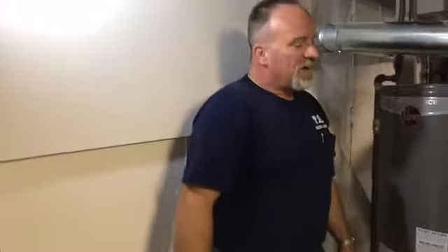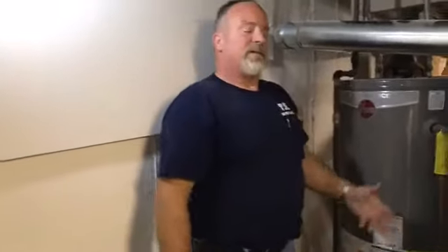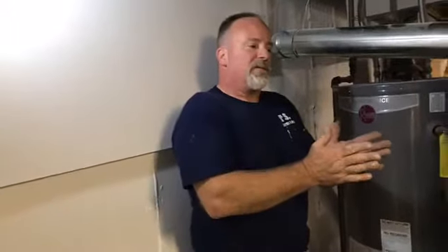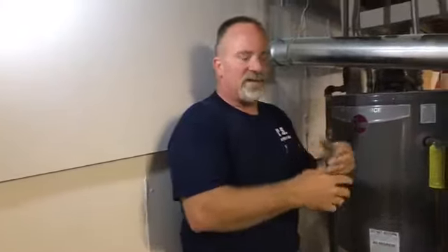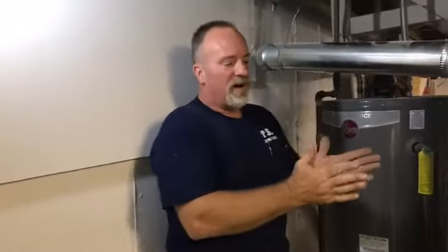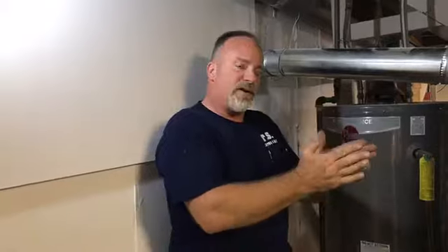And this furnace was actually put in by my brother-in-law, and this furnace is only probably 16, 17 years old. Right. So it's not like this was a really old furnace or anything like that. It actually needed to be replaced. The heat exchanger heats up, expands and contracts. The metal works back and forth, how many cycles a day, every year. It's just that the expansion and contraction will cause failures if not looked at.